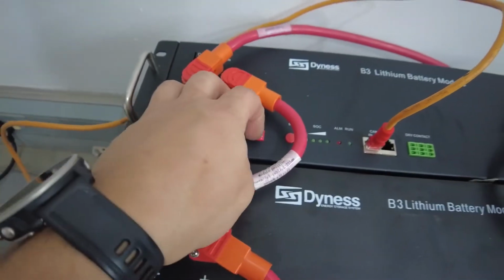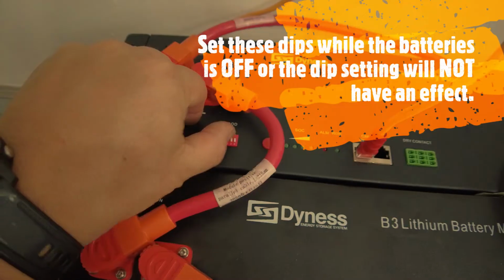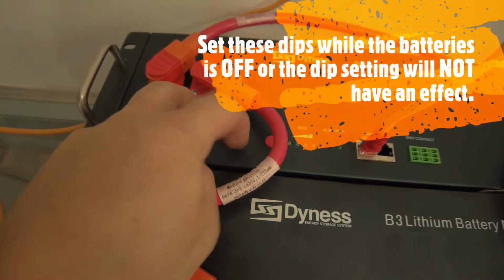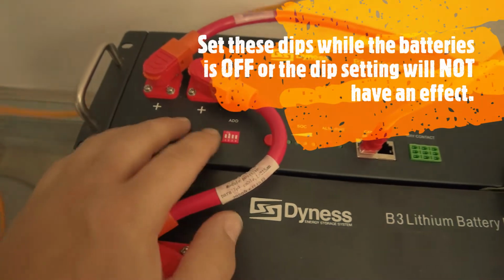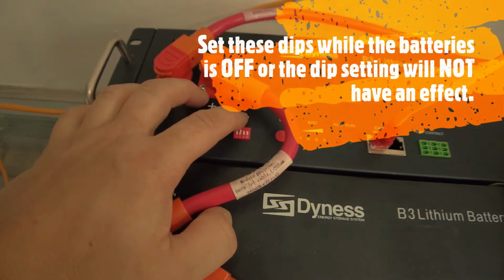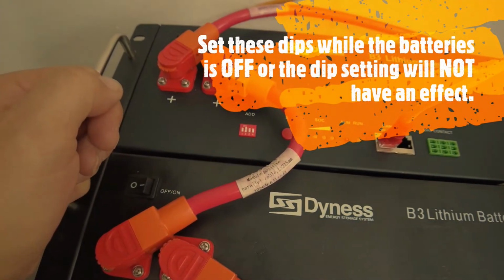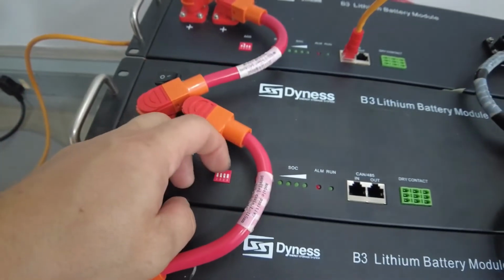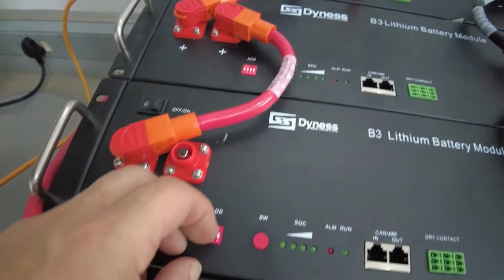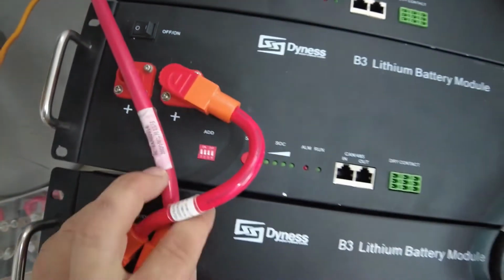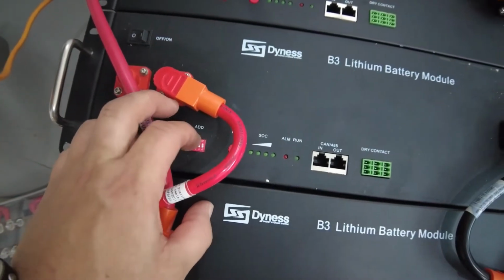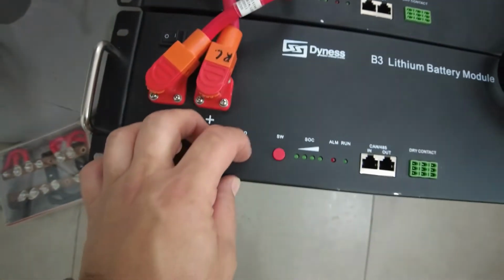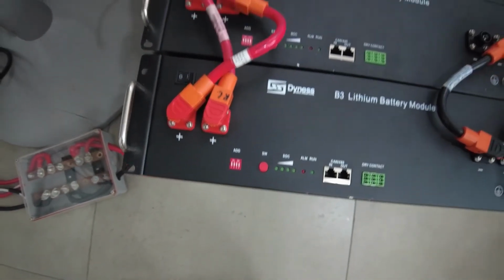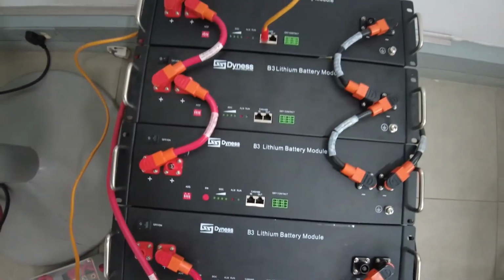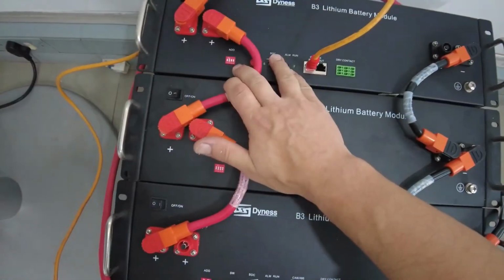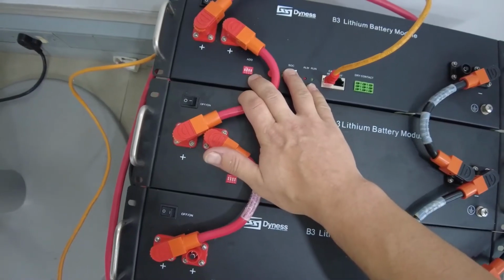So for this battery we need to change your dip switch to 0, 1, 0, 0, meaning your first dip is off, second dip on, third and fourth dips are off. For all of the remaining batteries you will leave the dips in the off position. They will then be your slaves. Now something I do tend to find is these dips do sometimes not make proper contact.